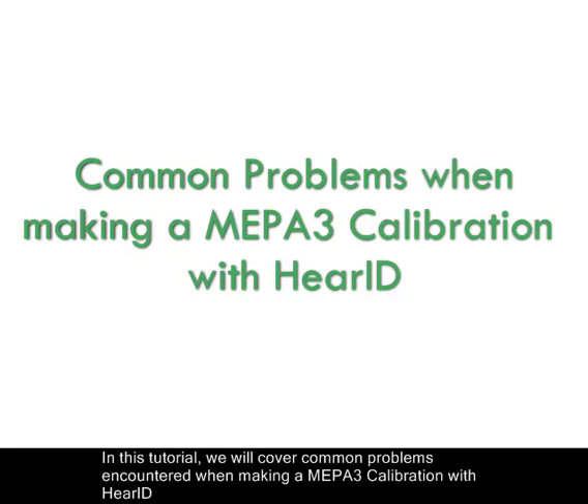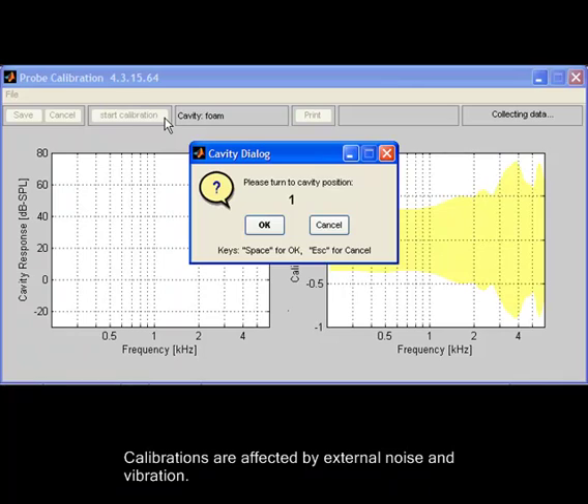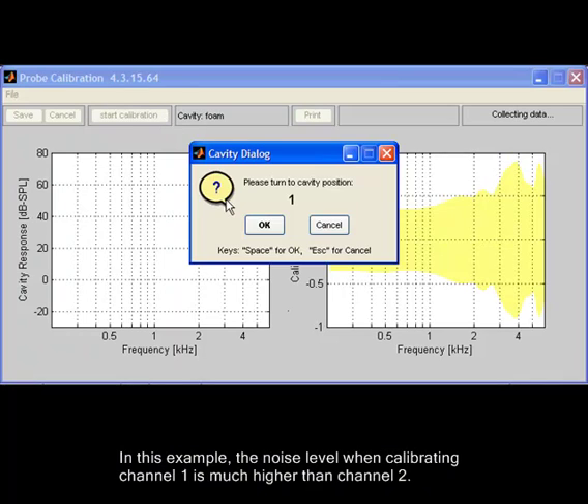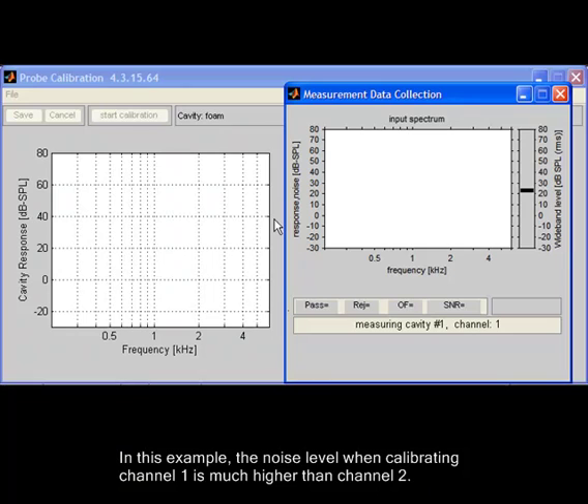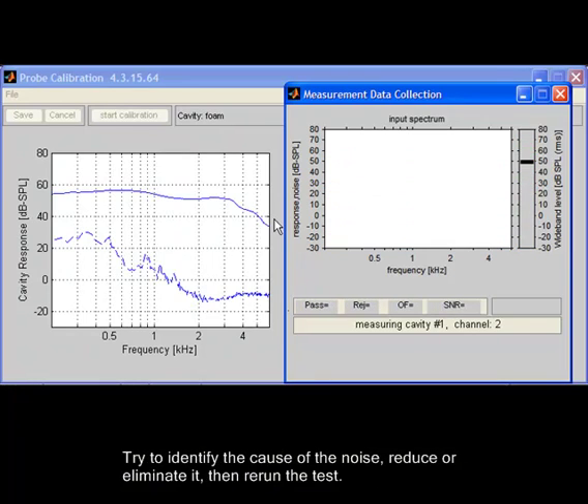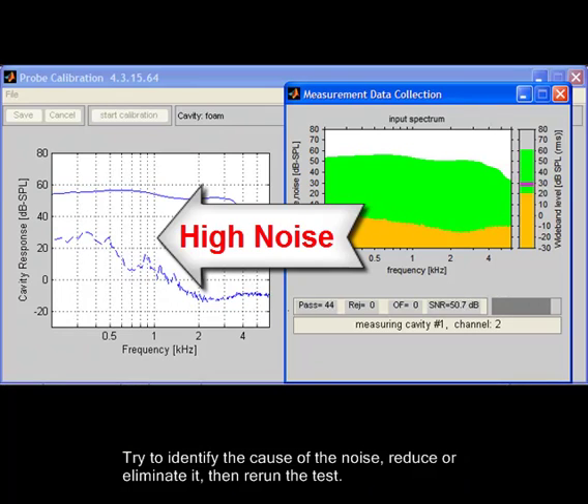In this tutorial, we will cover common problems encountered when making a MEPA 3 calibration with HearID. Calibrations are affected by external noise and vibration. In this example, the noise level when calibrating channel 1 is much higher than channel 2. Try to identify the cause of the noise, reduce or eliminate it, then rerun the test.